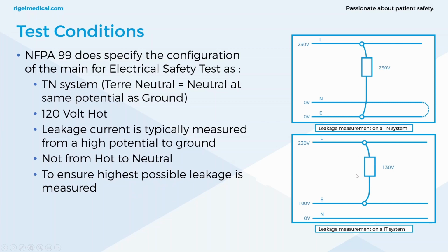Now on a non-TN system, the highest potential from phase to earth is not achieved because the leakage currents are limited to isolation levels of the supply system. So no valid leakage measurements are possible unless the safety analyzer is able to produce an internal ground at half the line voltage. Now, this is actually stated in NFPA 99 in one section. You might have already seen it, where it states that an adapter can be used temporarily to produce an internal ground. And this allows you to perform a test if you are carrying out a test in situ on the IT system. Now, our devices have an IT system detection and notification, which is a useful feature as it lets you know if you're on the wrong type of system.